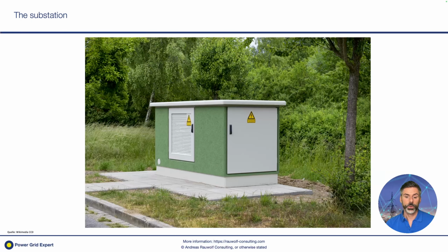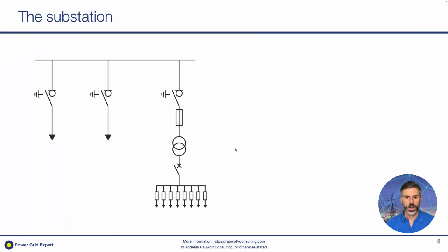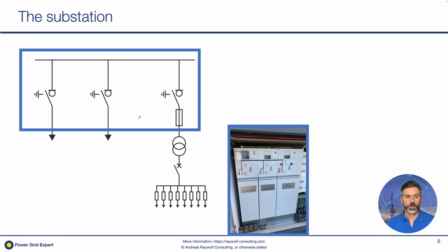So that for sure, that's a classic secondary substation in a concrete housing here. Modern style, of course, there's lots of different styles, metal clad housings, real brick houses, but that's, let's say, the most recent versions. And what's inside? Inside there is the medium voltage switchgear. The medium voltage switchgear has normally an incoming and an outgoing feeder. Here you can see an example how it looks in real life. And we have the feeder towards the transformer.